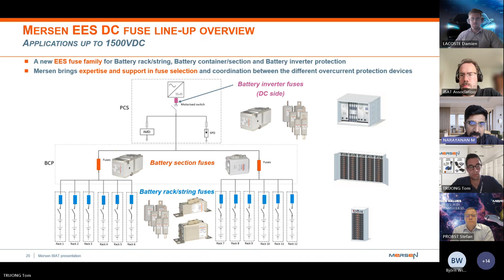And also when we go to the power conditioning system, or PCS, just above the section fuses column, we can size these DC side inverter fuses depending on where they are employed in the given energy storage system. Here we talk about 1500 volt DC as a system voltage, and these are some of the DC fuse lineups to show you.